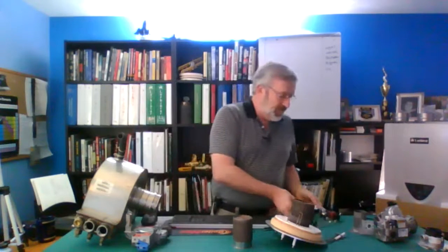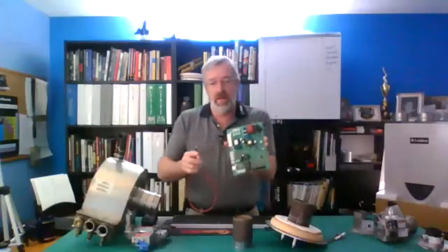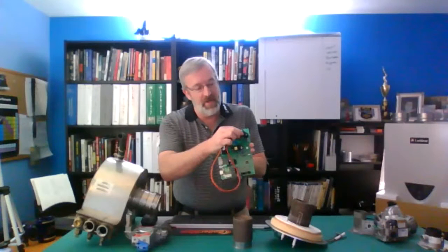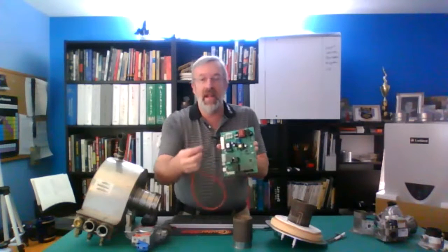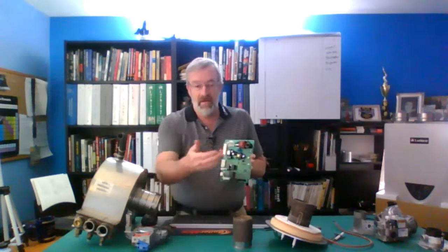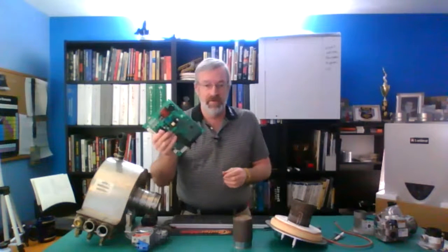If I don't spark here now, I'm gonna go back to my main control board, and I'm going to look at that ignition module, and I'm gonna disconnect from the ignition module, and I should see a spark from here to here. If I spark here to here, I didn't come out the end of my cable, I didn't come out the end of my igniter. Those are the 2 things I'm gonna troubleshoot. If I don't spark here, I'm gonna replace that. It's got that ignition module on it.